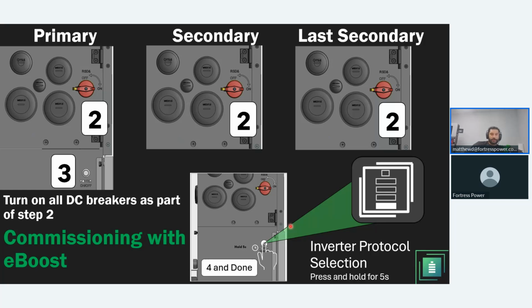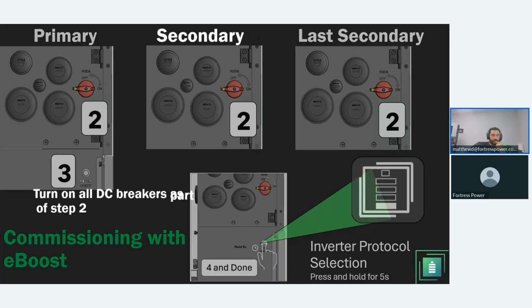So it would be inverter protocol. You're going to hold the button for 5 seconds, and then release it. And then the frames of the battery are going to blink, right? They're going to blink and let you know which protocol you're at. You're going to see the outer frames, and then you're going to see the SOC bar. The SOC bar has to always be at the 25% mark, which is the bottom bar, okay? So this is 25, 50, 75, and 100. So typically, you should be able to see it at the first bar.